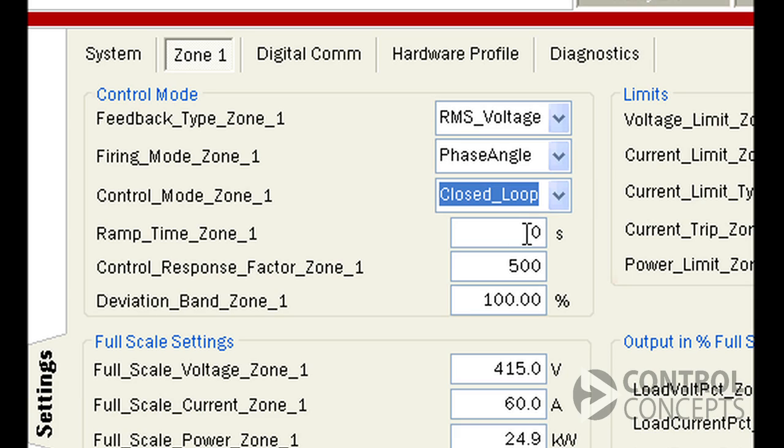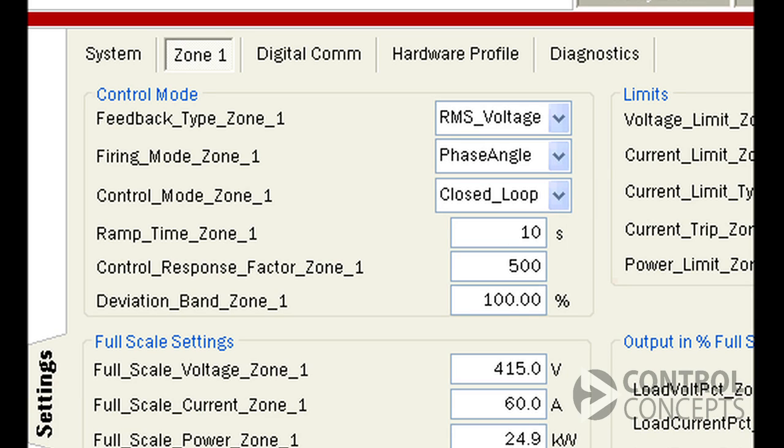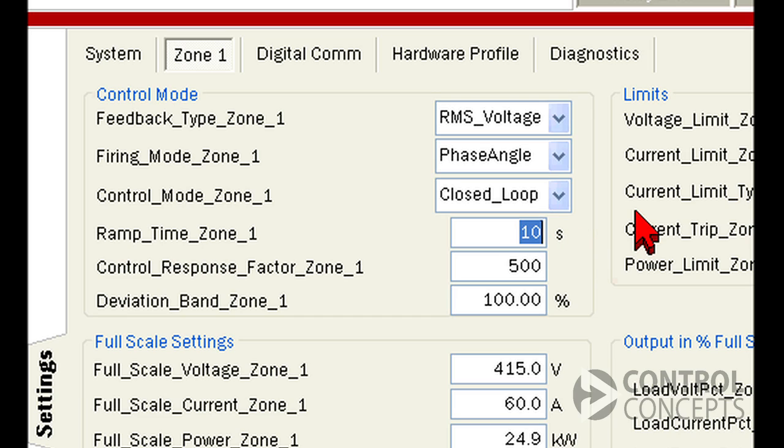Your ramp time limits how fast the controller turns on. Entering 10, for example, tells the controller to take 10 seconds to ramp up to your target set point. Zero means this feature is disabled.